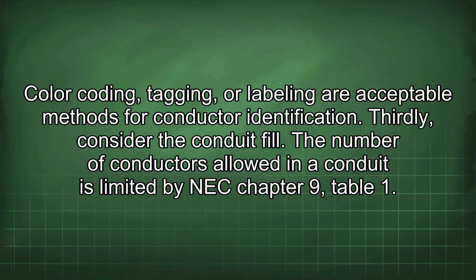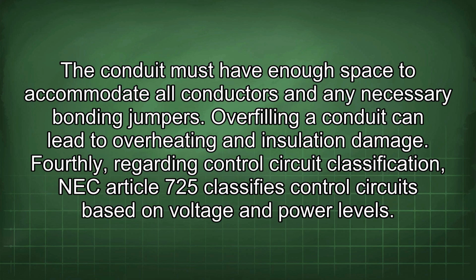Thirdly, consider the conduit fill. The number of conductors allowed in a conduit is limited by NEC Chapter 9, Table 1. The conduit must have enough space to accommodate all conductors and any necessary bonding jumpers. Overfilling a conduit can lead to overheating and insulation damage.